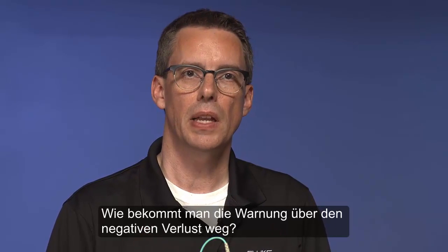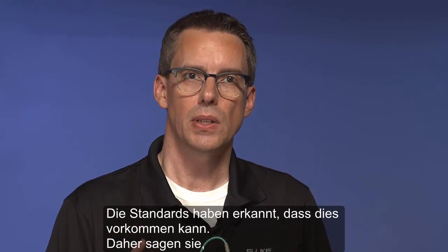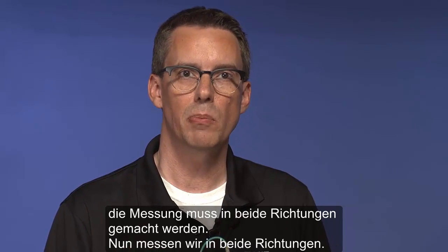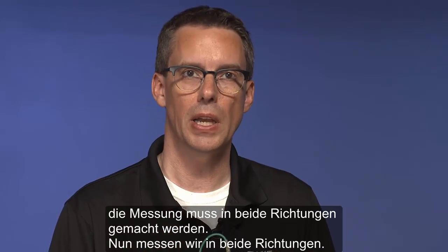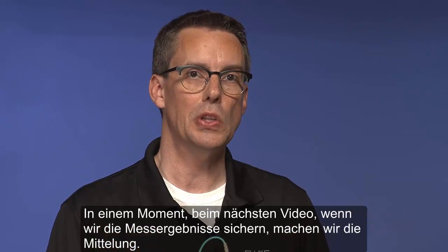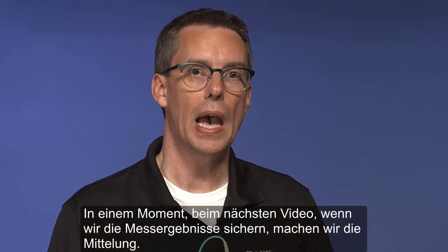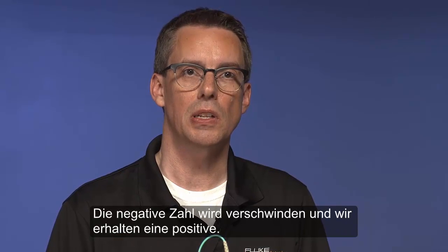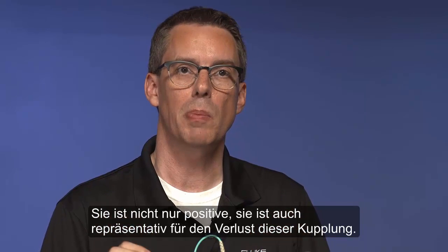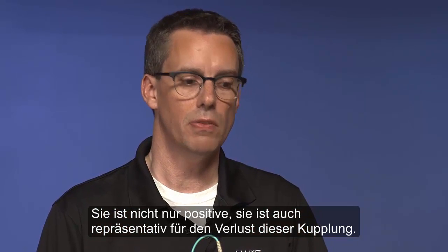Now, how do you get rid of that negative loss warning? The standards recognize that this can happen. And so what they tell you to do is to test it in both directions. Now, we're testing it in both directions. The second part of that equation is you then download the results and you average the directions that you tested in. So in the next video, when we download the test results, we're going to do that averaging, and that negative number is going to disappear, and we're going to end up with a positive number. And not only is it going to be positive, it's going to be more representative of the loss that's in that connection.